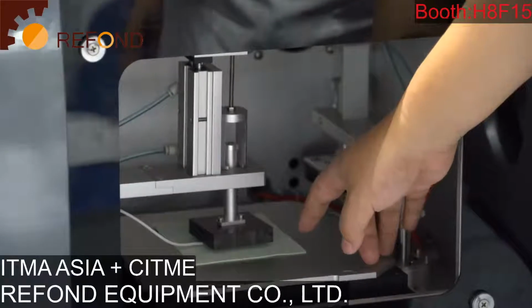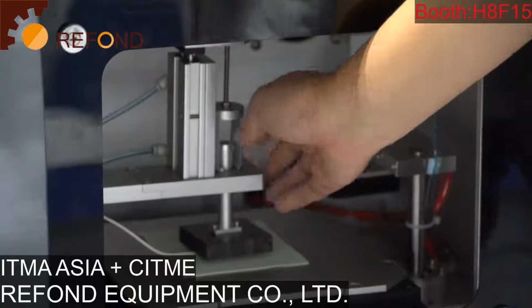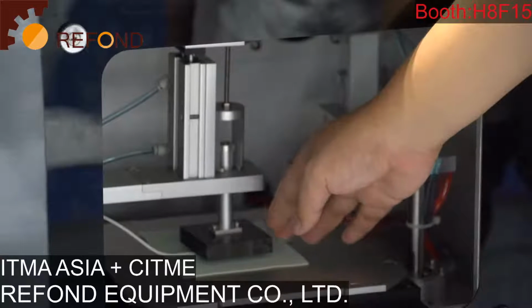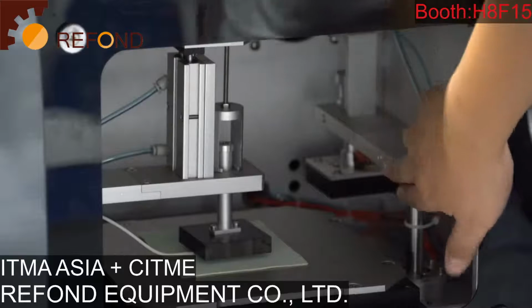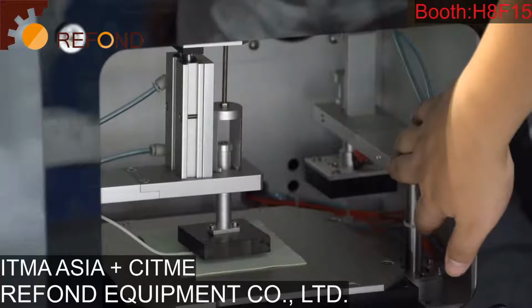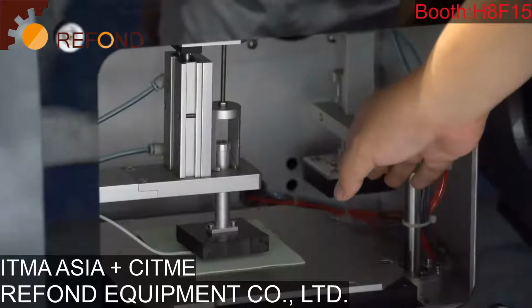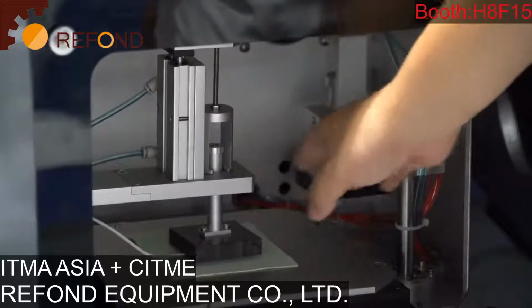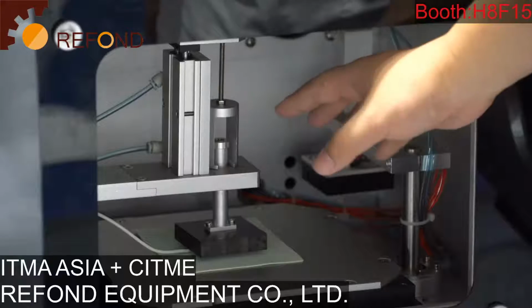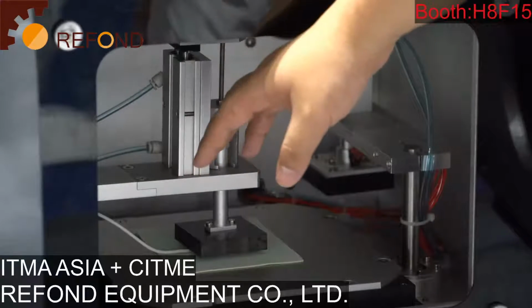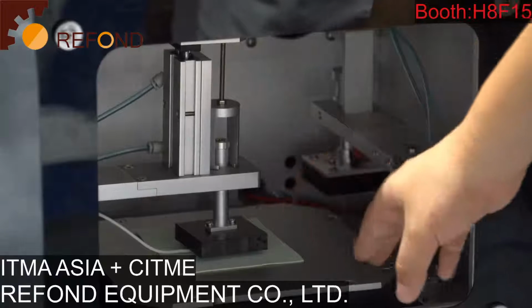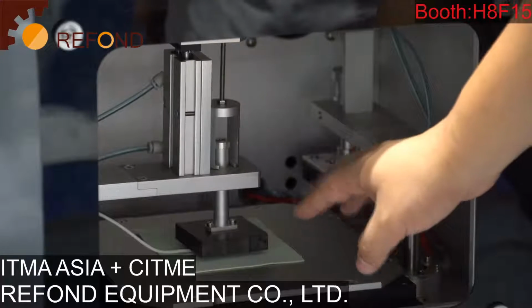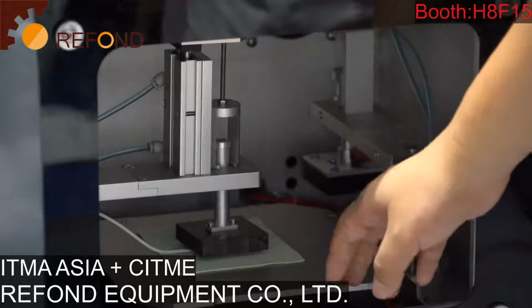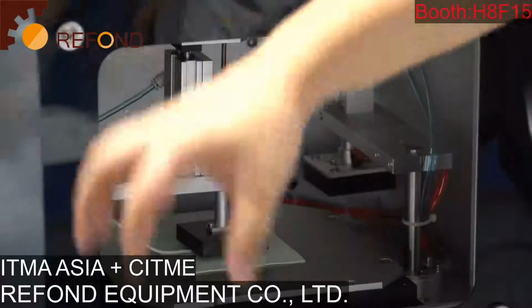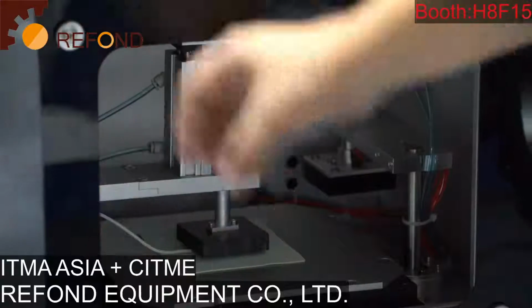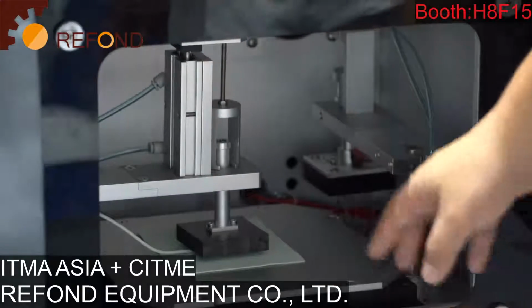the specimen. On the left side, on this arm is the cool feeling test head, and then on the right side is the heat conductivity test head. Both test heads are controlled pneumatically by air cylinders, so the movement of them is very repeatable and precise. It eliminates the human error related to the older designs, which requires you to put the test head onto the sample manually.